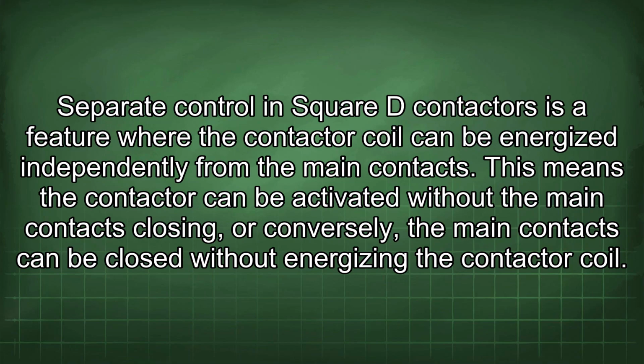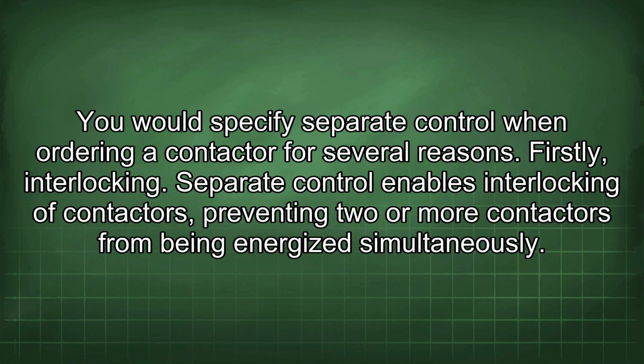Separate control in Square D contactors is a feature where the contactor coil can be energized independently from the main contacts. This means the contactor can be activated without the main contacts closing, or conversely, the main contacts can be closed without energizing the contactor coil. You would specify separate control when ordering a contactor for several reasons.